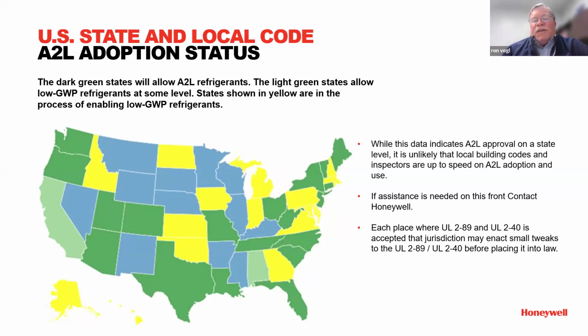And one thing I didn't really mention is that if you're making equipment, one thing is to have the other approvals, but you have to sell listed equipment - that is UL listed or ETL listed equipment. Those standards are being revised as we speak. UL 2-40 is just about done, and that is under air conditioning. So that's moving faster, and equipment suppliers are going to be selling A2L equipment now, basically - I think you can take orders for it. 2-89 deals with the refrigeration side of things, and that's a little bit slower.